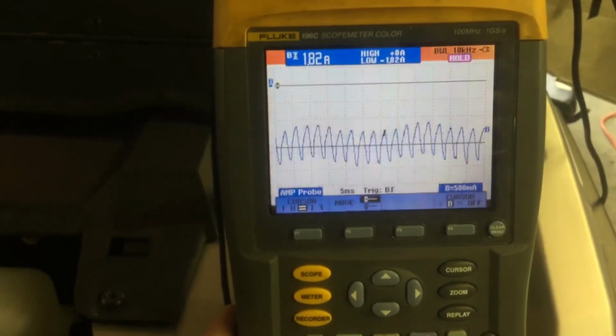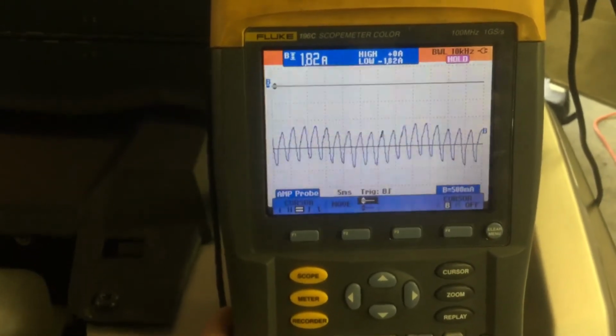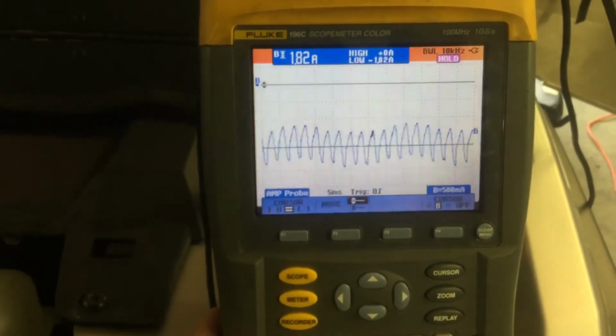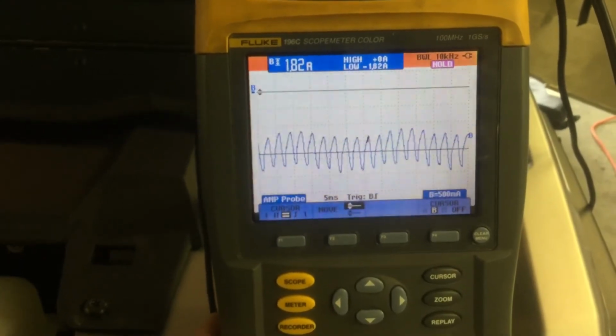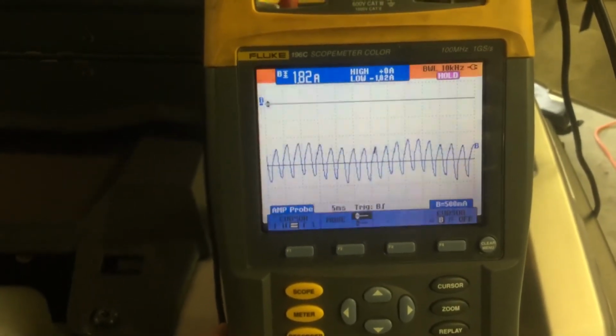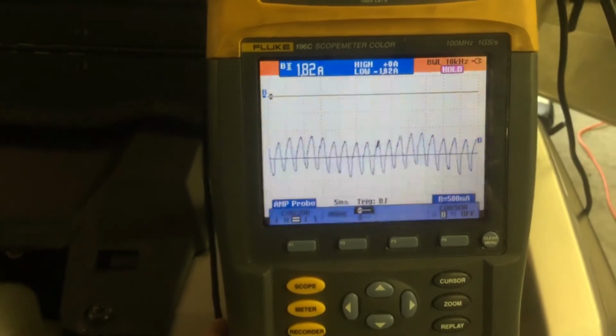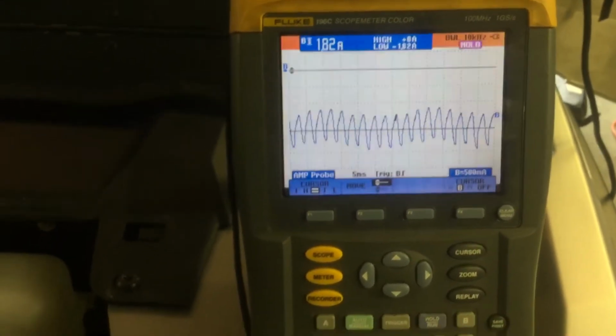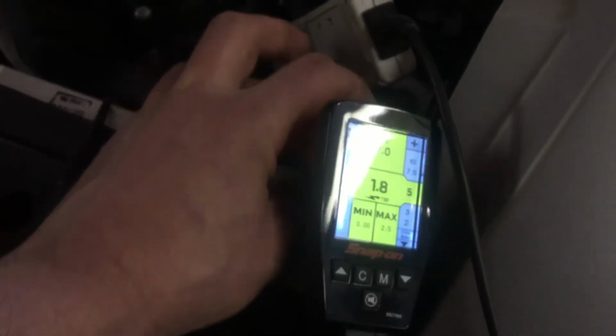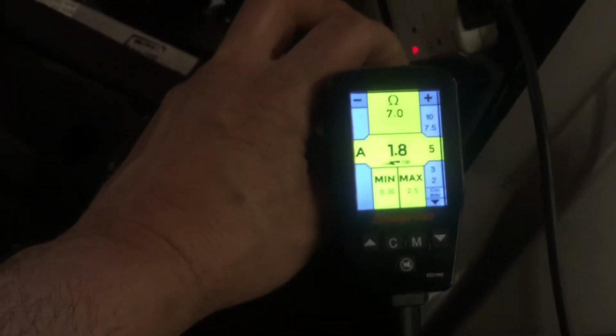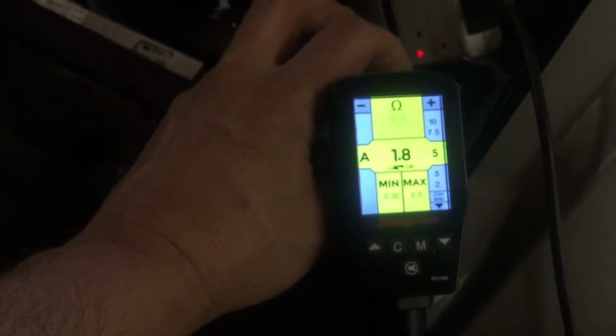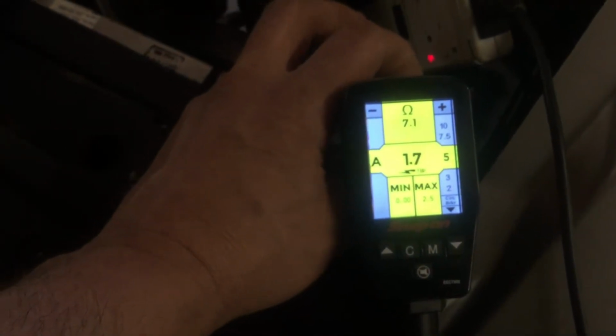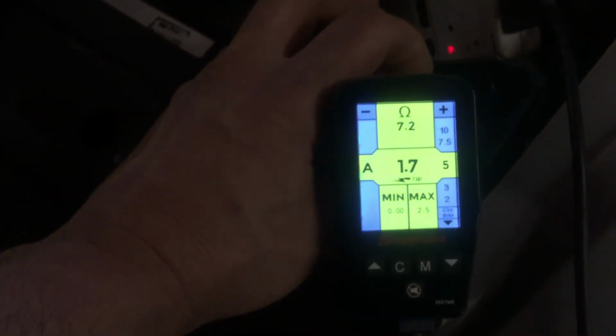Considering my current clamp was calibrated to my scope meter, which I did calibrate and it was darn close, I got about 1.82 amps of draw on my current clamp. And over here, pretty darn close, 1.82, somewhere in there, with 7.2 ohms of resistance.